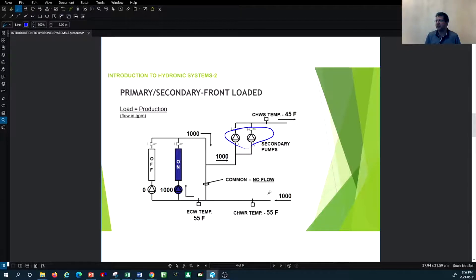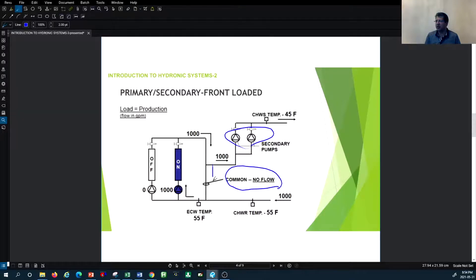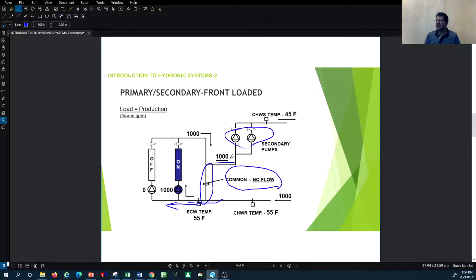On the return side, you expect a 10-degree temperature difference, so you gain heat to the chilled water system and return it at 55°F back into the primary loop. At this condition, you do not expect any flow in the common pipe — flow moves in one direction on the supply side and straight back on the return side. Since primary and secondary loads are equal, there is no flow in the common pipe. This is one possible scenario.